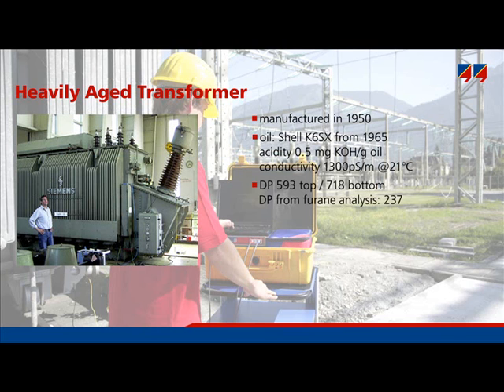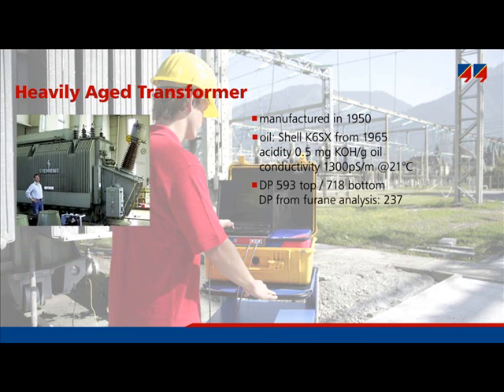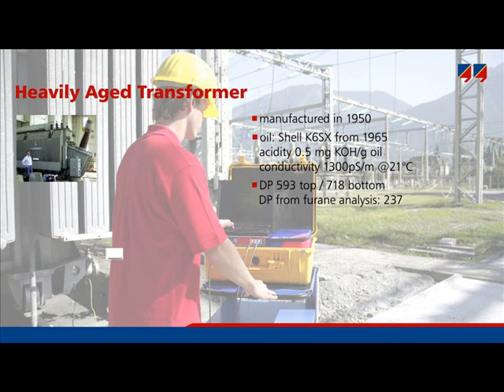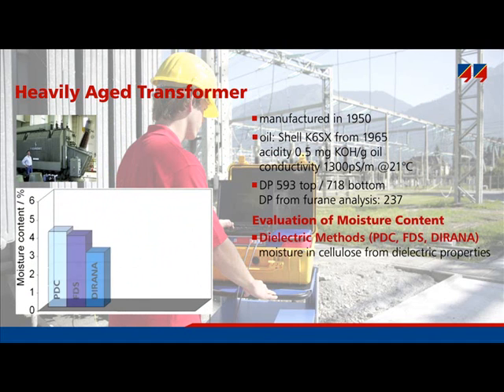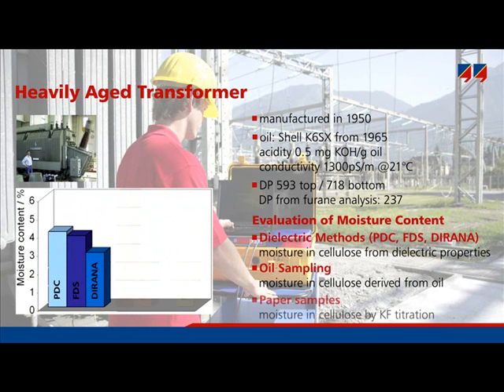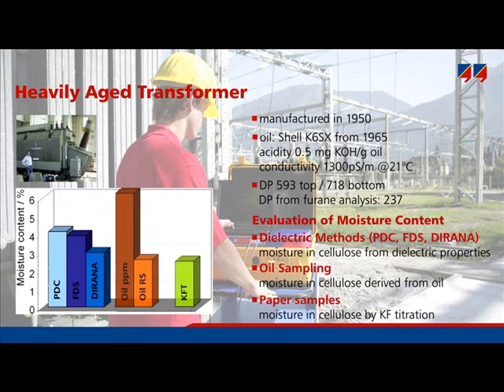It appears that the transformer's problem was with the oil rather than with the solid insulation. Various techniques were applied to evaluate the moisture content: dielectric response methods such as PDC, FDS, and DIRANA; oil sampling methods using the Oomen equilibrium chart based on relative saturation; and finally the analysis of paper samples taken from the transformer. The moisture content values obtained using these methods range from 2.5 to 6%.